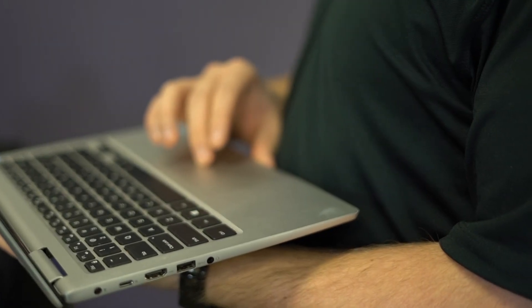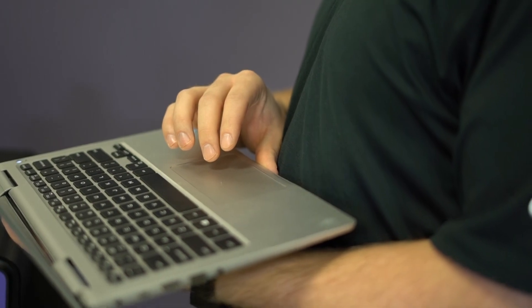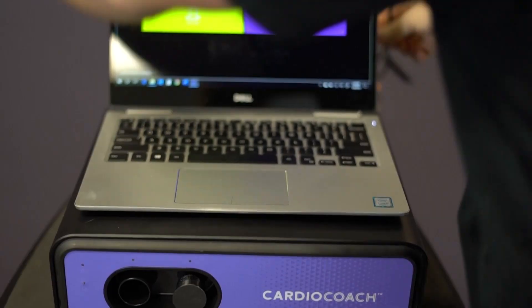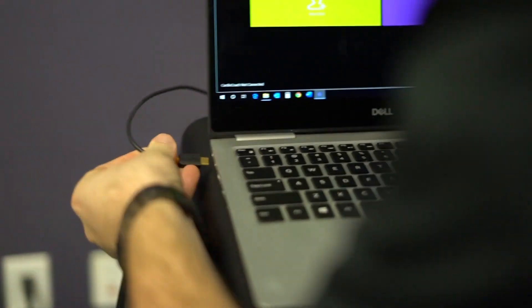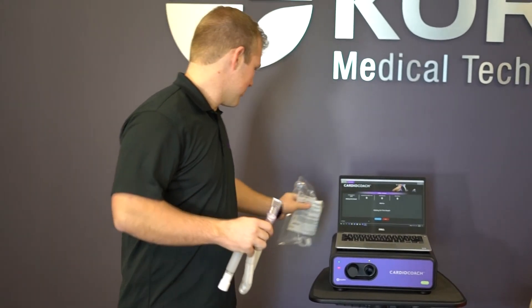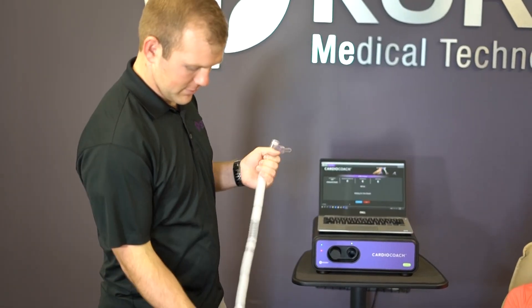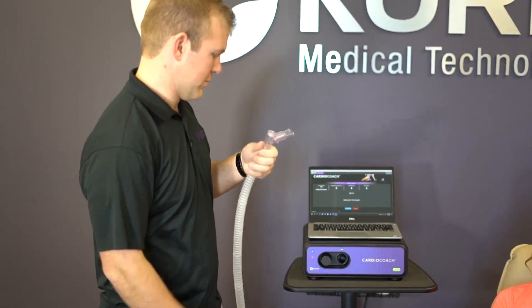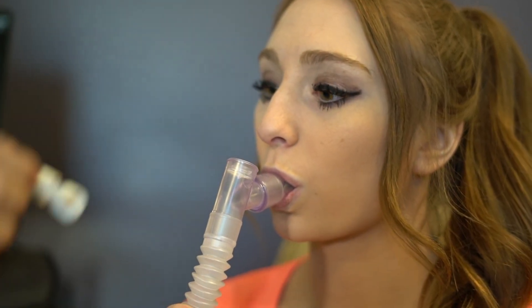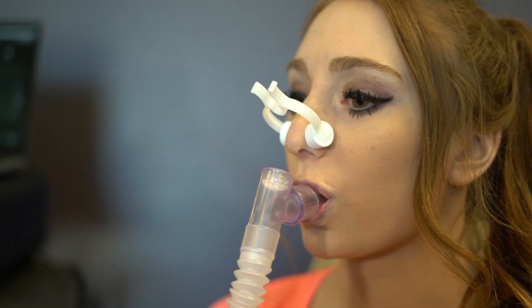The Cardio Coach has been designed to function with Bluetooth connectivity. Your Quick Start Kit includes a USB cable to connect your Cardio Coach to the computer in the unlikely event that you encounter interference with the Bluetooth signal. KORR strongly recommends the use of a KORR-manufactured MetaBreather Max to ensure the measurement accuracy of a resting metabolic rate test. KORR cannot guarantee the ability of this product to accurately measure resting metabolic rates when a breathing device other than a MetaBreather Max is used.